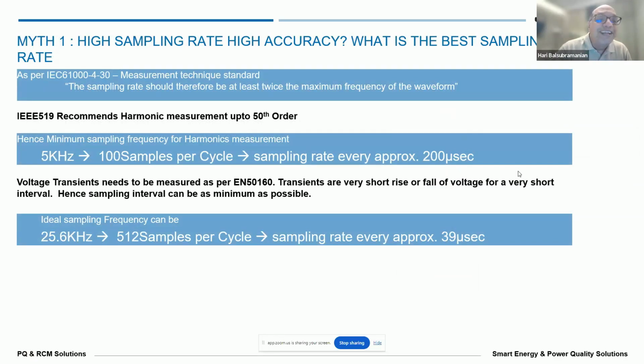So, very interestingly, IEC 61000-4-30 says the sampling rate should be at least twice the maximum frequency of the waveform, which means 100 hertz can be the sampling frequency. But for 100 samples per cycle, you need to have 5 kilohertz.